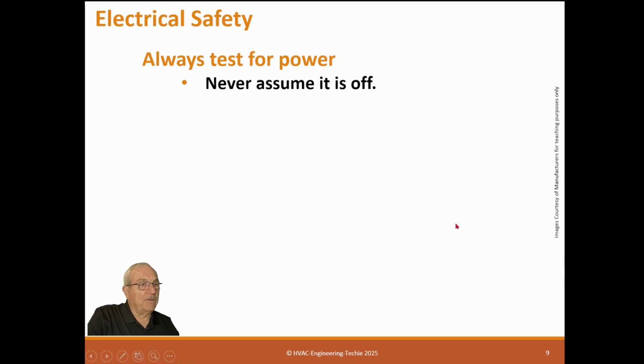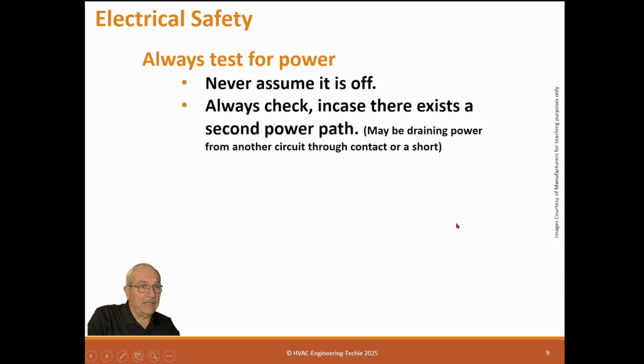Always test for power. Never assume it's off. Always check in case there exists a second power path. Now, it can be a second power path, but it can also be a ground feed or a short feed. So it could be another circuit that happens to be exposed to your circuit, and its problem can shard onto yours. So you need to be careful. Always check. It's a thing you must do, unless, like us guys, you work with 120 or 24 volt. It's not a big deal. For 24 volt, it ain't gonna hurt you that bad. But 480 volt, it will absolutely get you. So you got to be really careful about that.